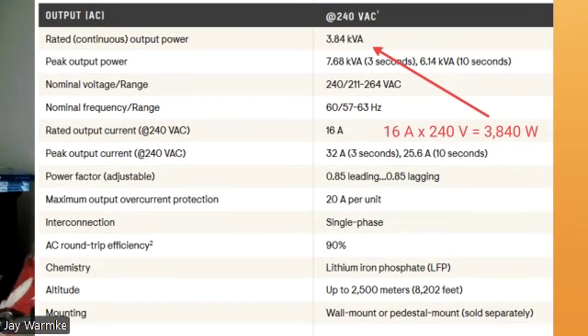When sizing your loads at any one time, you cannot run more than 3,840 watts of load continuously. There are surges though, their peak output is about double that for 3 seconds, like when a motor, such as on your refrigerator, spikes for a couple of seconds. It can handle that, but you need to know the continuous load capability for whatever you're hooking up. It's only 3,840 watts, which matters when figuring out what loads you want to back up. If you tried to throw an air conditioner on this single battery, forget it, it'll blow right past that limit immediately.